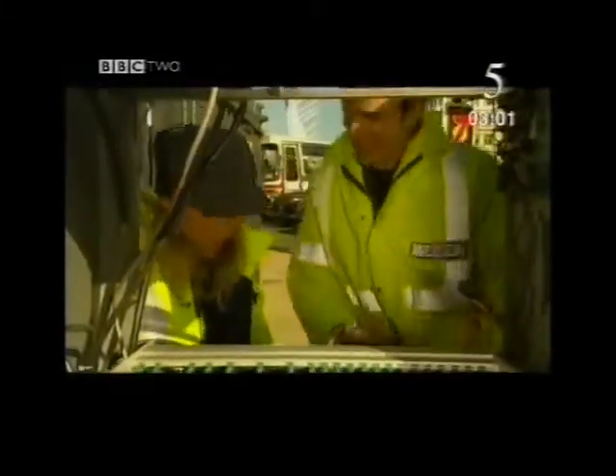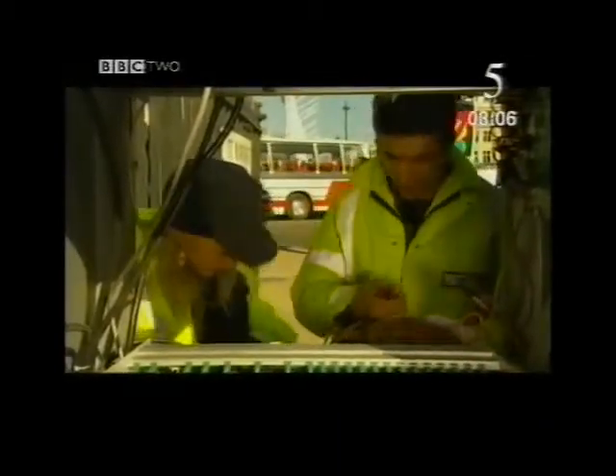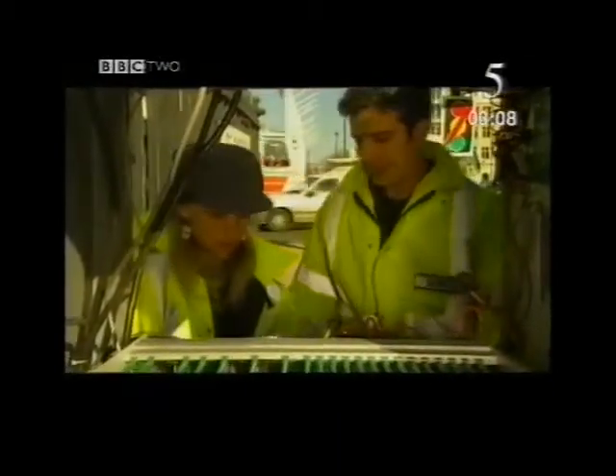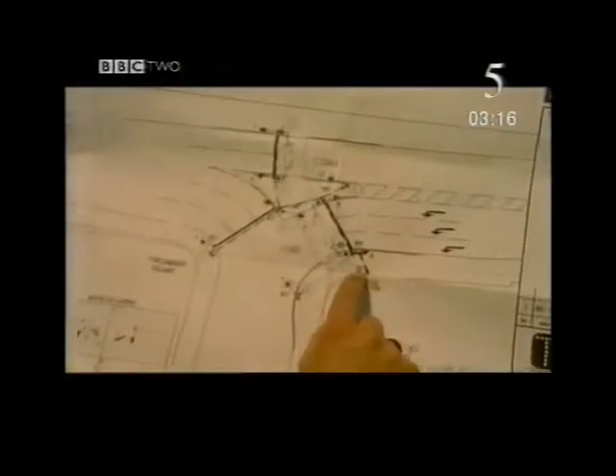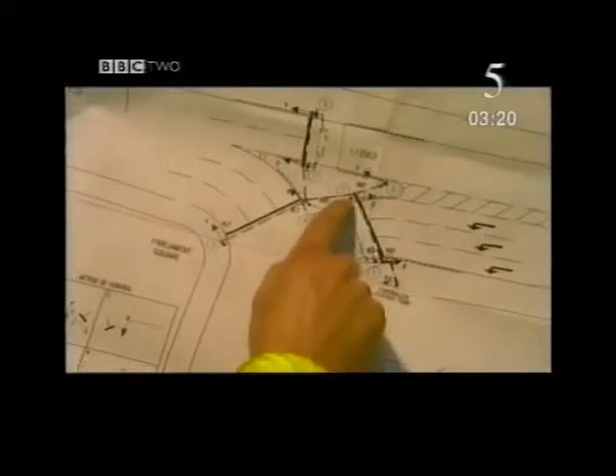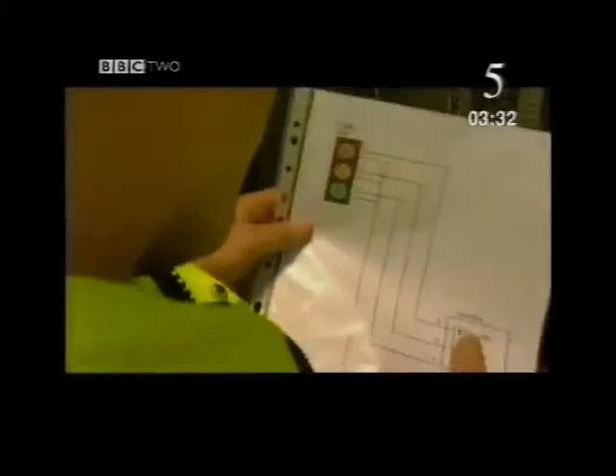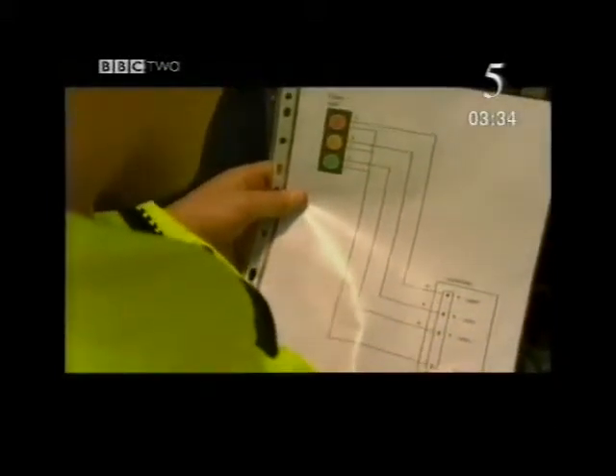This looks really complicated. Yes, well, we've got to find the circuit that we want to test. So have you got that circuit diagram? We'll have a look at this one first. OK, here we are at the controller. We're interested in this post here — that's the one that's not working. That's right, number five. So these are the red, amber, greens, and here is where we'll be testing for continuity.